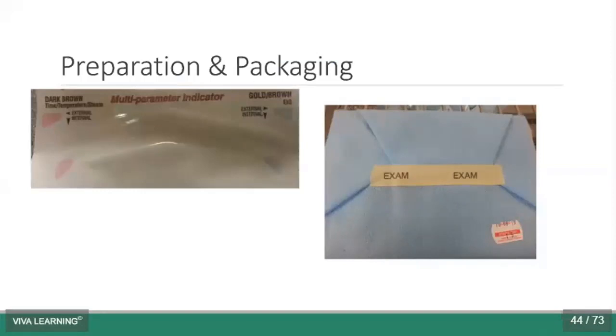So you see on the peel view pouch, we've got the little arrow that changes colors on the inside of that seal as well as the one on the outside. They can be single parameter or multi-parameter. And with cassettes, you need to have the autoclave tape on the outside, and you want to have an indicator on the inside too. A common observation I get in dental offices is that we have those instrument cassettes, we have the autoclave tape, but we don't have anything on the inside. We don't have a chemical indicator on the inside.